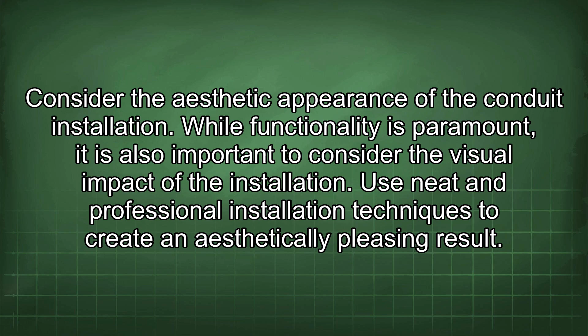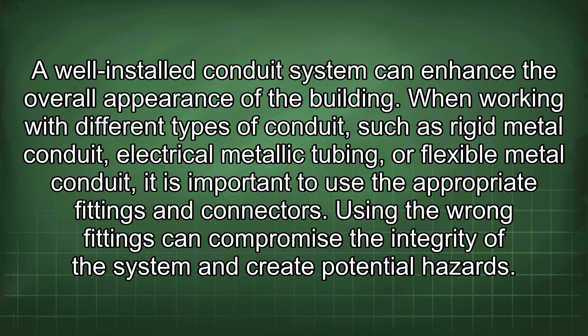When working with different types of conduit, such as rigid metal conduit, electrical metallic tubing, or flexible metal conduit, it is important to use the appropriate fittings and connectors. Using the wrong fittings can compromise the integrity of the system and create potential hazards. Always use fittings that are specifically designed for the type of conduit being installed. Finally, remember that electrical work can be dangerous.